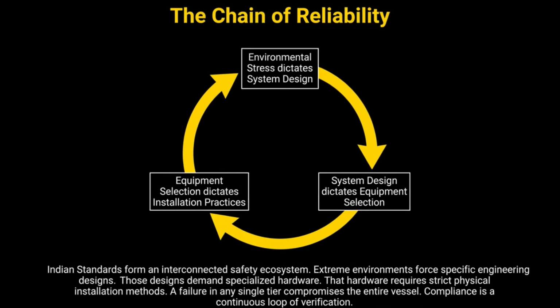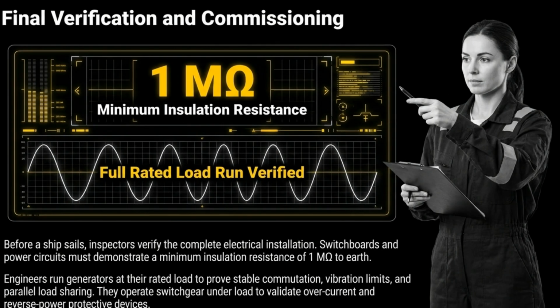Environmental stress, system design, and installation practices are interconnected. Failing at any stage compromises the entire vessel's safety. Finally, before a ship sails, inspectors commission the systems, verifying insulation resistance and performing full load runs to confirm that all protective devices function correctly.